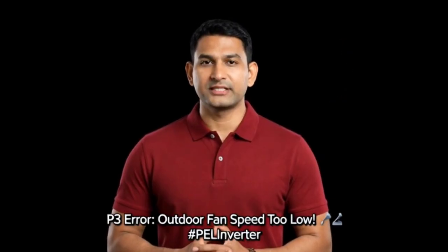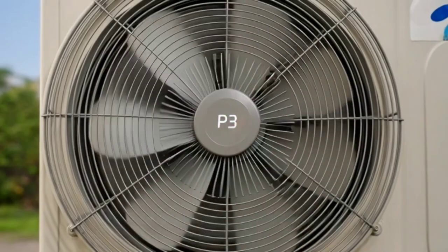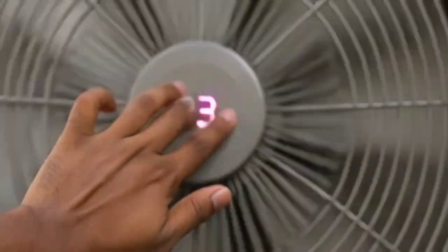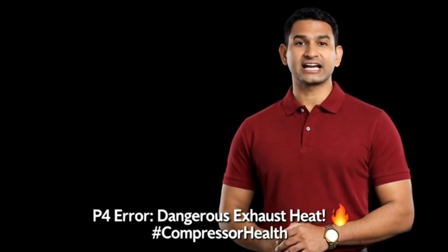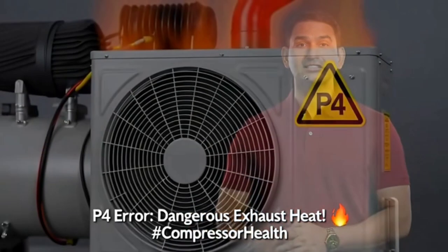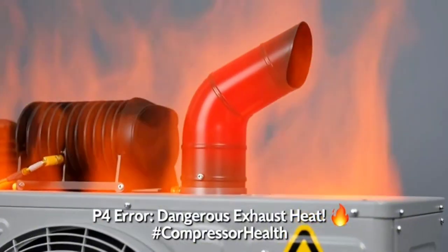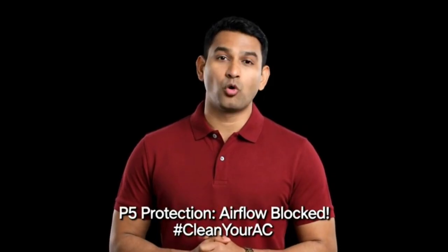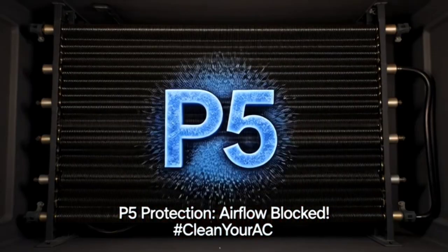P3 means the outdoor fan is spinning too slowly or is jammed. P4 means the compressor's gas temperature is dangerously high. P5 means the coils are too cold. Check for dirty filters immediately.